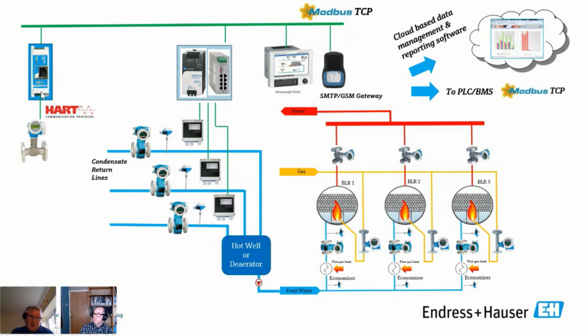Some sites will only look at Ethernet IP or Profinet or other digital protocols. But one useful way of taking all of the energy data from these flow computers or individual meters is to use something like Modbus over Ethernet. It's a very widespread, very effective protocol, and most flow computers from different manufacturers have that option as well.